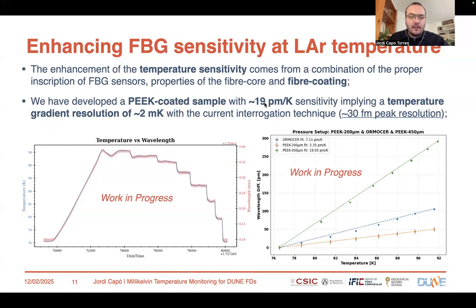We have worked with several manufacturers to coat our fibers with different materials, and we have developed a PEEK coated sample that offers 19 picometers per Kelvin sensitivity in the range of temperatures of interest. And this implies a temperature gradient resolution using this technology of the order of 2 millikelvin, considering the current interrogation technique that allows us to track the peak position with a resolution of something like 30 femtometers.